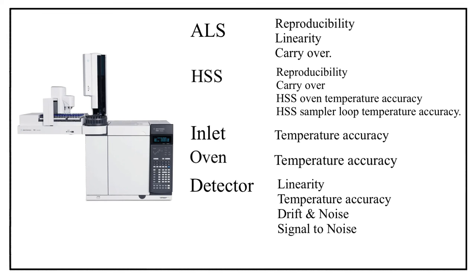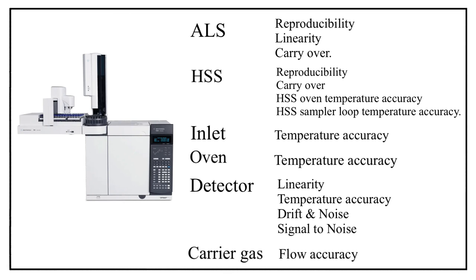Now comes the last calibration parameter, which is related to carrier gases. All the carrier gases are checked using a flow accuracy test parameter, and generally a digital flow meter is used to carry out this test.